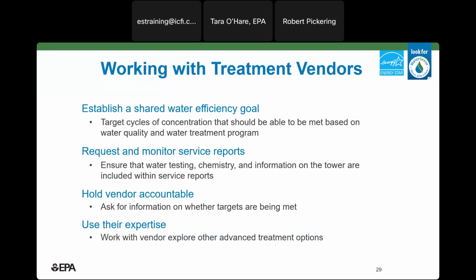So calculating that target cycles of concentration and establishing a water treatment program may sound complicated, and it can be. Oftentimes it is complicated. That's why most buildings commonly contract this out to a water treatment vendor. This is someone who comes on site or comes to your facility once every couple of weeks or months and checks up on the water treatment program. They'll take some measurements, they'll monitor chemicals, and make sure that everything is in working order.